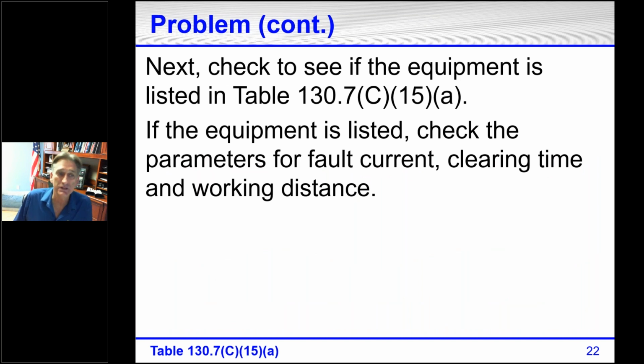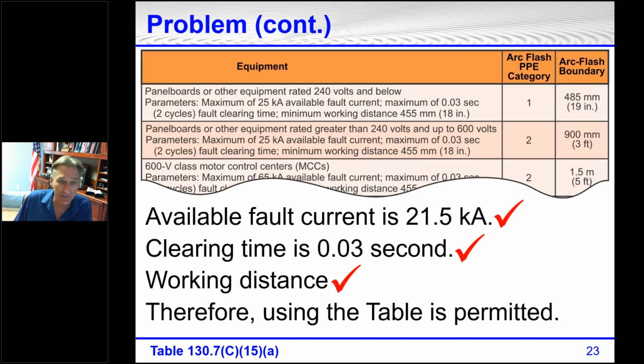Next, we're going to check to see if the equipment is listed in table 130.7C15A. If it's listed, we're going to check the parameters. This is 480 volt equipment, phase to phase, so it's the second row down: panel boards or other equipment rated greater than 240 up to 600 volts. So that's the row we're looking at. Parameters, maximum of 25,000. I gave you 21,500 amps. Check. That's good. Clearing time 0.03 second, which is the maximum clearing time. And I also gave you the working distance of 18 inches. Therefore, we can use this table.